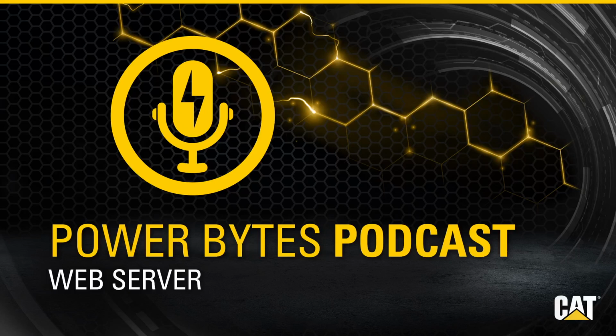Sounds like a great way to assure that all the things are working and talking together prior to turning over the system to the IT folks to bring the system inside their firewall at final handover. Do you agree? Definitely. Technicians can feel confident handing over the genset to IT after assuring the Cat side is working properly and that they've verified Ethernet communications are working from the genset web server to their PC.